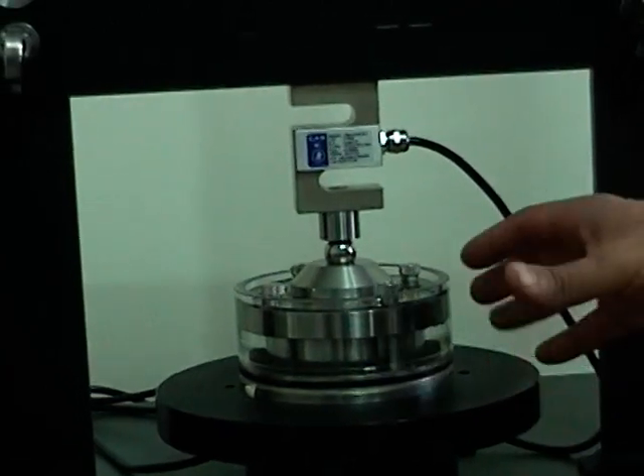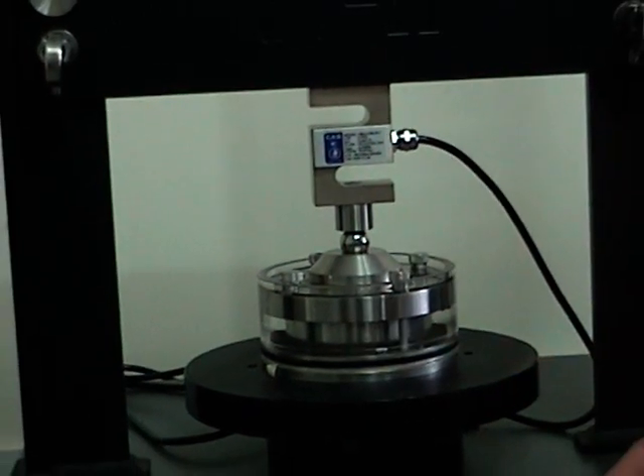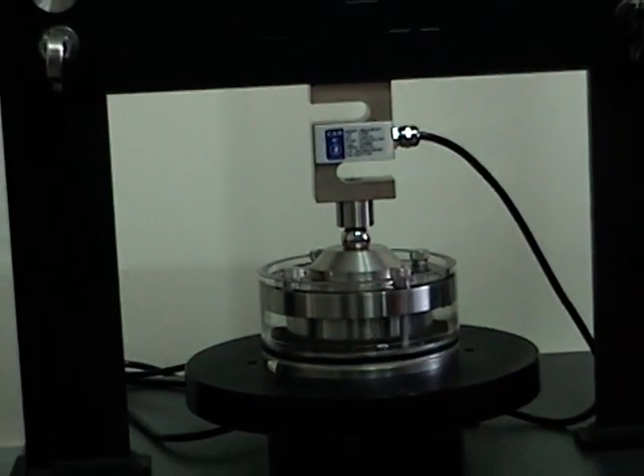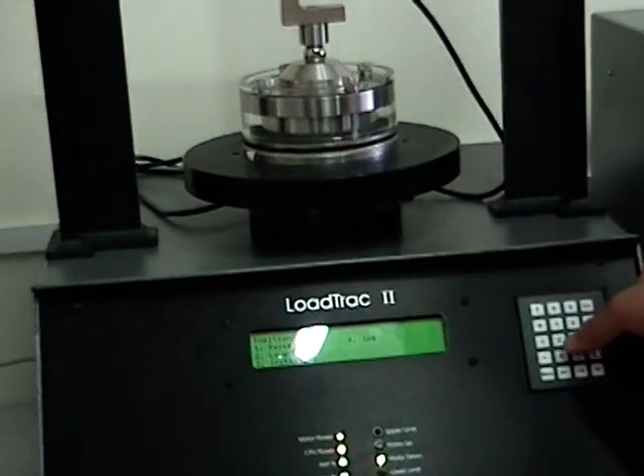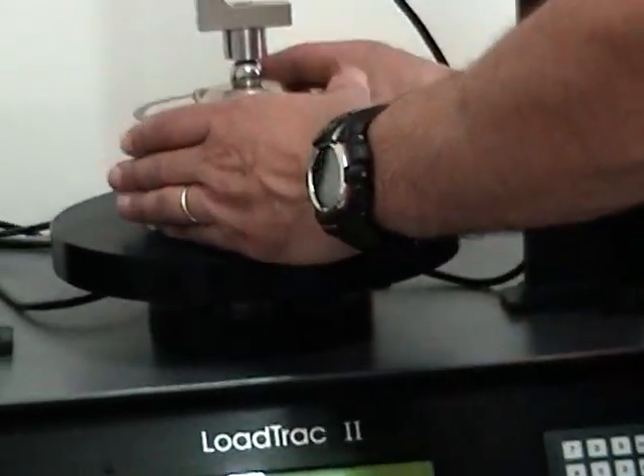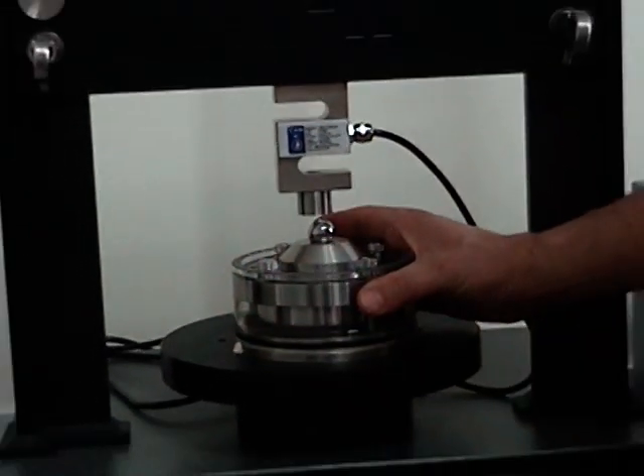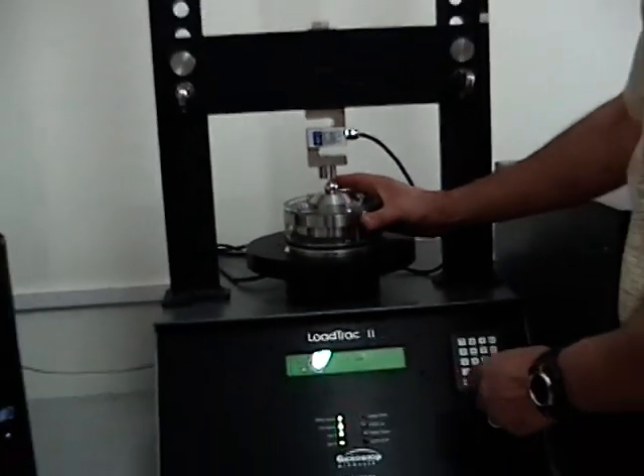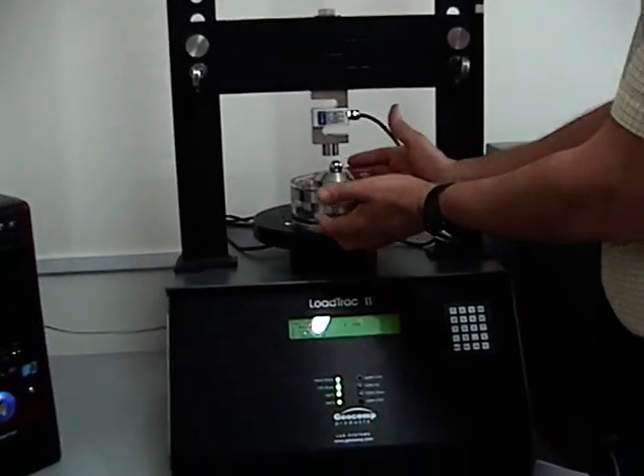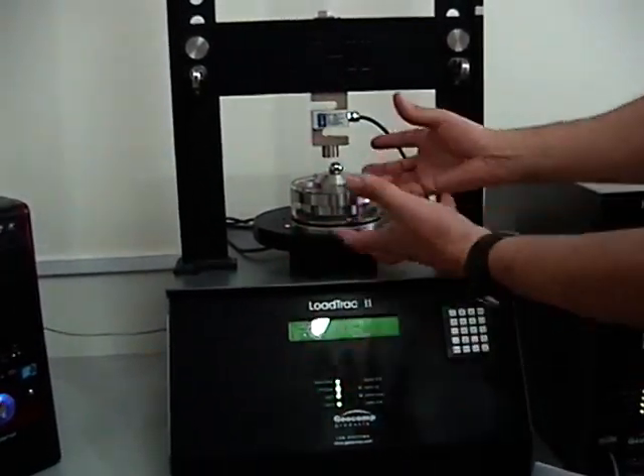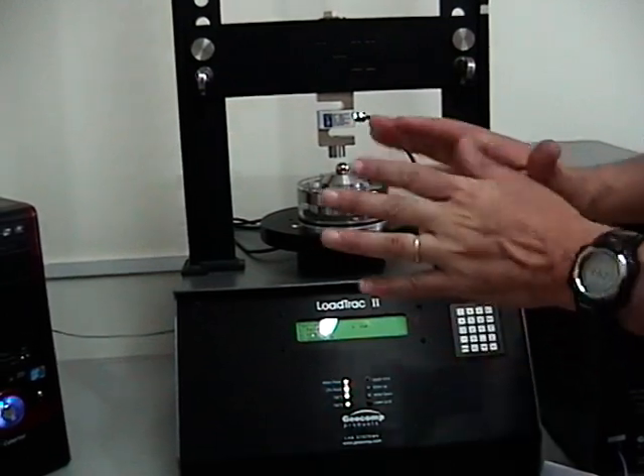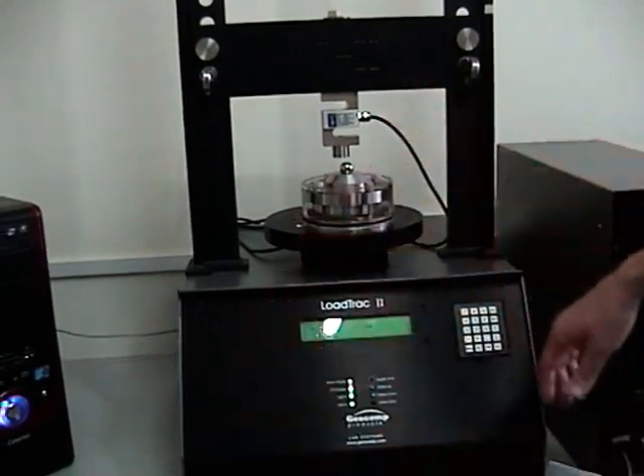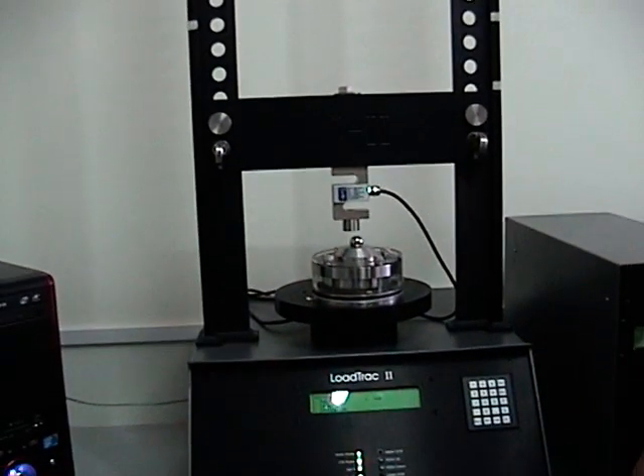Now the platen is going to move down to zero load, so there won't be any load here and you should be able to remove it. If it does not go to zero, you can go to Position, Lower, we have to go faster. Now the sample, you can take it out, dump the water, and take your water measurements, and you are done with the test.